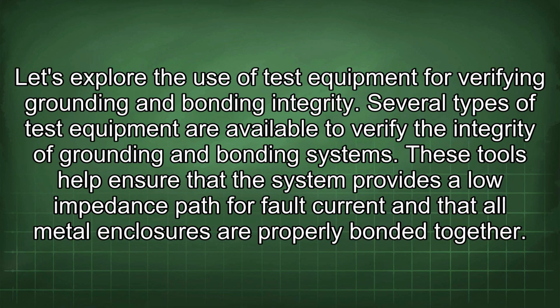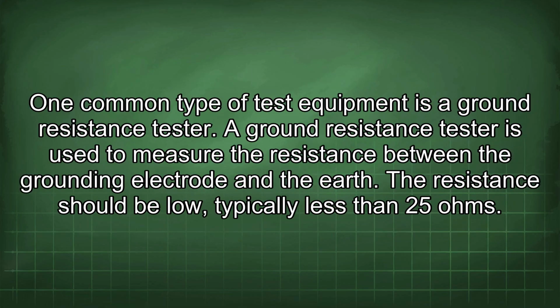Let's explore the use of test equipment for verifying grounding and bonding integrity. Several types of test equipment are available to verify the integrity of grounding and bonding systems. These tools help ensure that the system provides a low impedance path for fault current and that all metal enclosures are properly bonded together. One common type of test equipment is a ground resistance tester.